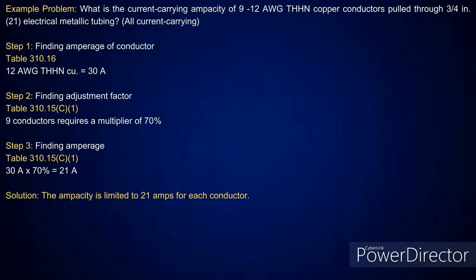The top of Table 310.16 tells you it's for three or less current-carrying conductors at an ambient temperature of 86°F. Anything above that, you go look at Table 310.15B and Table 310.15C. For number 12 THHN with nine current-carrying conductors, I look at Table 310.16 — using the 90°C column based on NEC 110.14C — and a number 12 gives me 30 amps. Since I have four or more, I apply an adjustment factor from Table 310.15C1: for nine current-carrying conductors, the multiplier is 70%. So 30 amps × 70% limits each conductor to 21 amps — enough for 20-amp circuits.